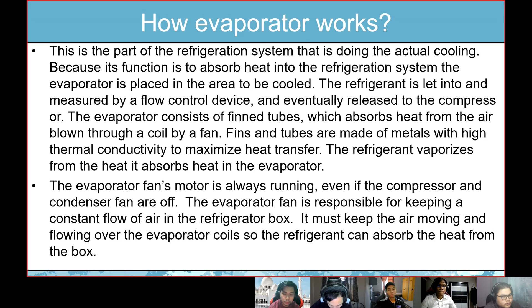Next, the evaporator fan's motor is always running, even if the compressor and condenser fan are off. The evaporator fan is responsible for keeping a constant flow of air in the refrigerator box. It must keep the air moving and flowing over the evaporator coil so that the refrigerant can absorb the heat from the box. That's all for the evaporator.